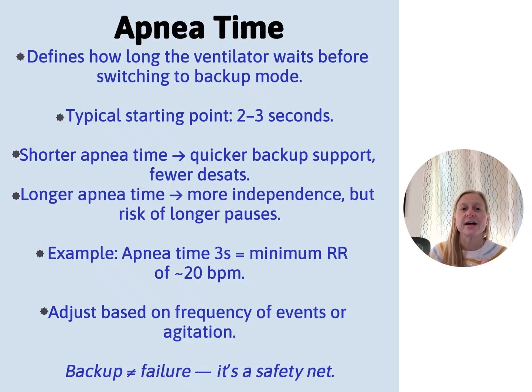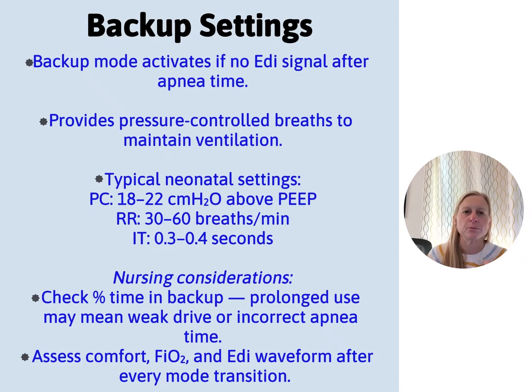So the apnea time defines how long the ventilator waits before it switches to backup mode. All ventilators are going to have that backup mode. So the shorter apnea time is a quicker backup support. Longer apnea time is more independence. It's based on the frequency of events or agitation. If the baby goes into backup, it's not failure. It's just what they need at that moment. So keep that in mind as you go through there. But apnea time and the NAVA level were the two things for me. If my NAVA level was high or my apnea time was low, I was like, we're still on a lot of support. And that's your quick glance to see where you're going. And I hope that helps you with a mental picture.